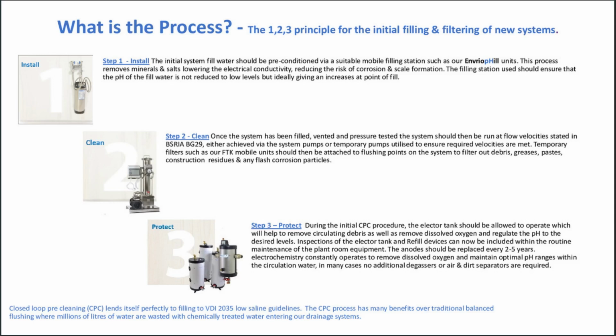So install. The initial system fill water should be preconditioned by a suitable mobile filling station, such as our EnviroPHill units. The process removes minerals and salts, lowering the electrical conductivity, reducing the risk of corrosion and scale formation. The filling station should be used to ensure the pH of the fill water is not reduced to low levels, but ideally giving an increase at point of fill.